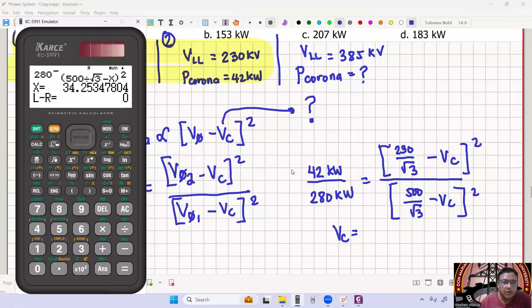So 42 over 280 is equal to 230 over square root of 3 minus x, the quantity squared, over 500 over square root of 3 minus x, the quantity squared. So ilan yung critical disruptive voltage? 34.25 kilovolts. Ayan. So let's go to condition number 3.